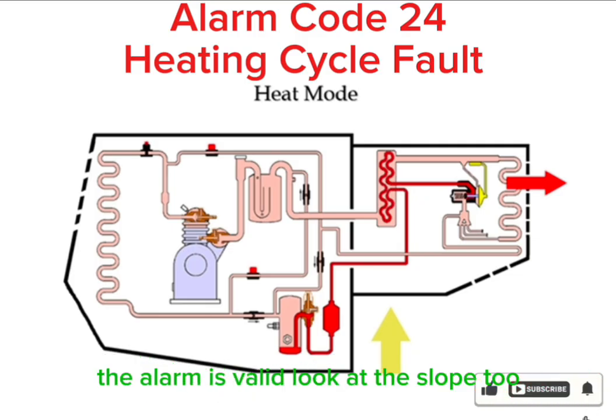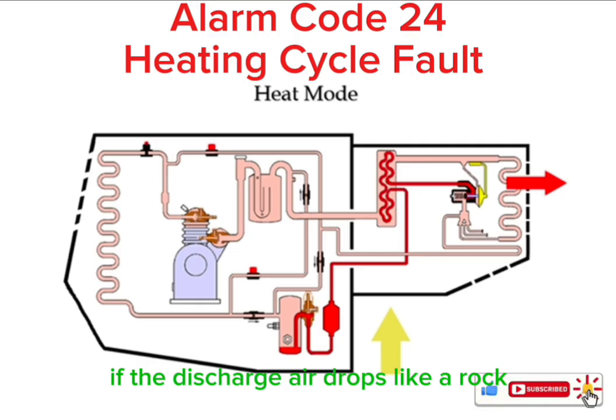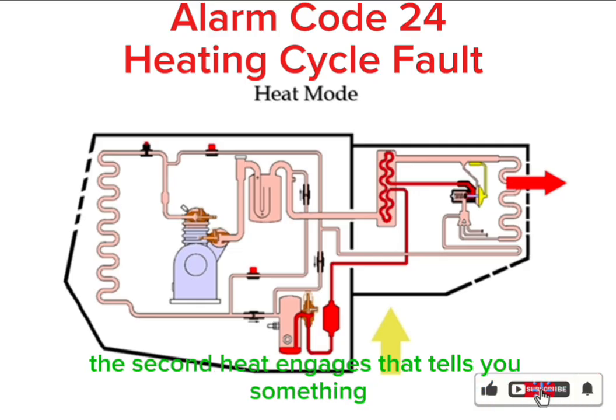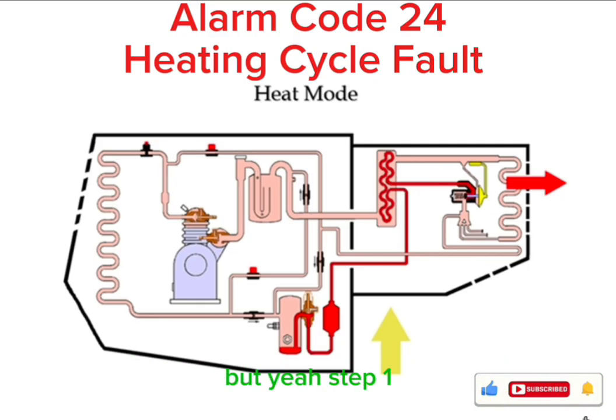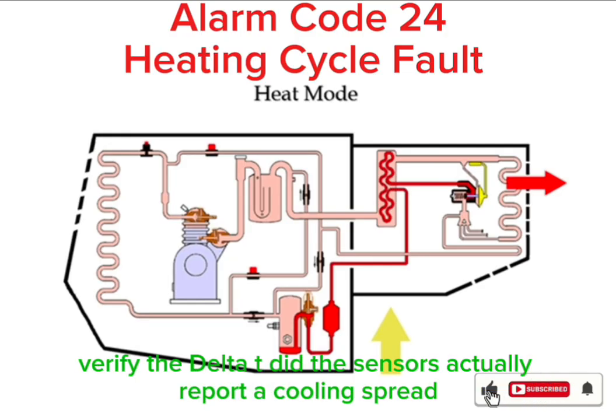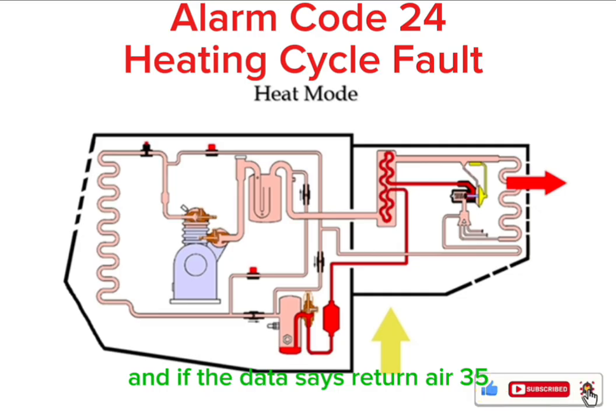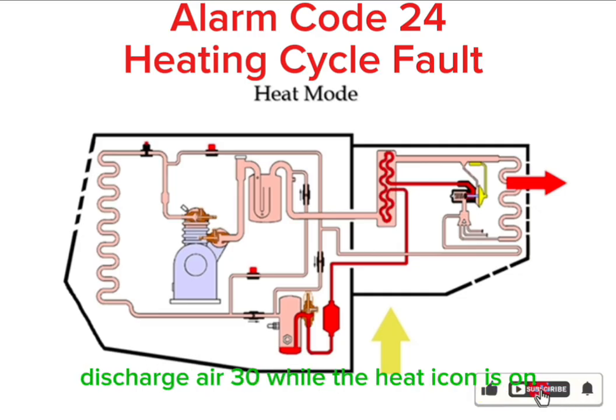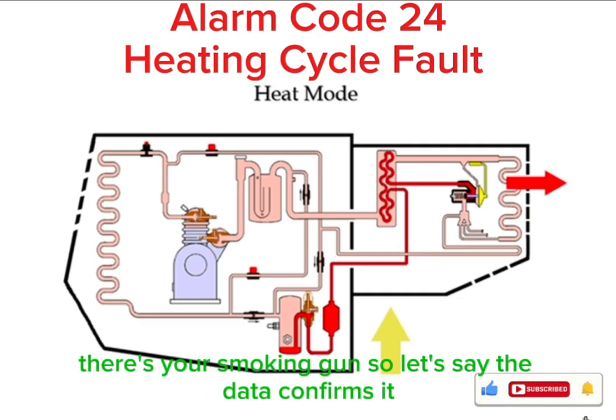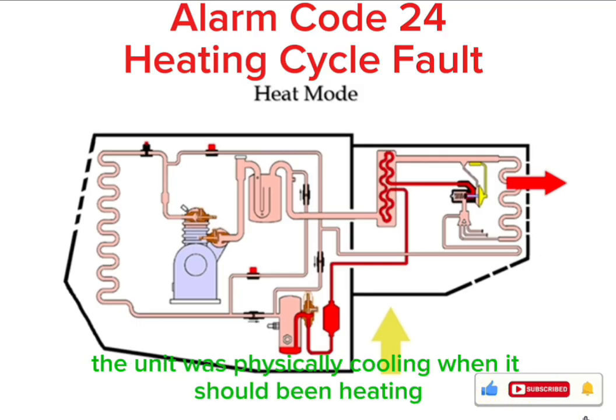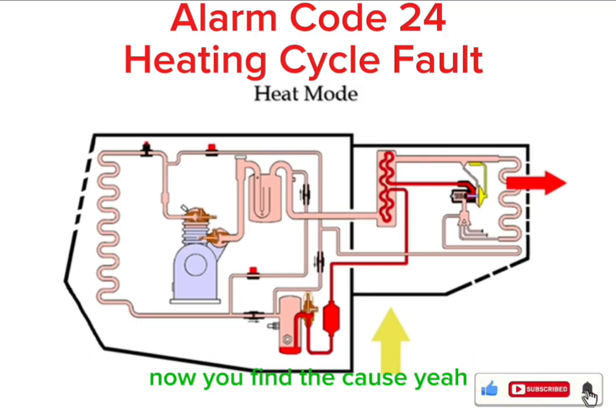Look at the slope, too. If the discharge air drops like a rock the second heat engages, that tells you something. But yeah, step 1, verify the delta T. Did the sensors actually report a cooling spread? And if the data says return air 35, discharge air 30, while the heat icon is on, there's your smoking gun. So let's say the data confirms it. The unit was physically cooling when it should have been heating. Now you find the cause.